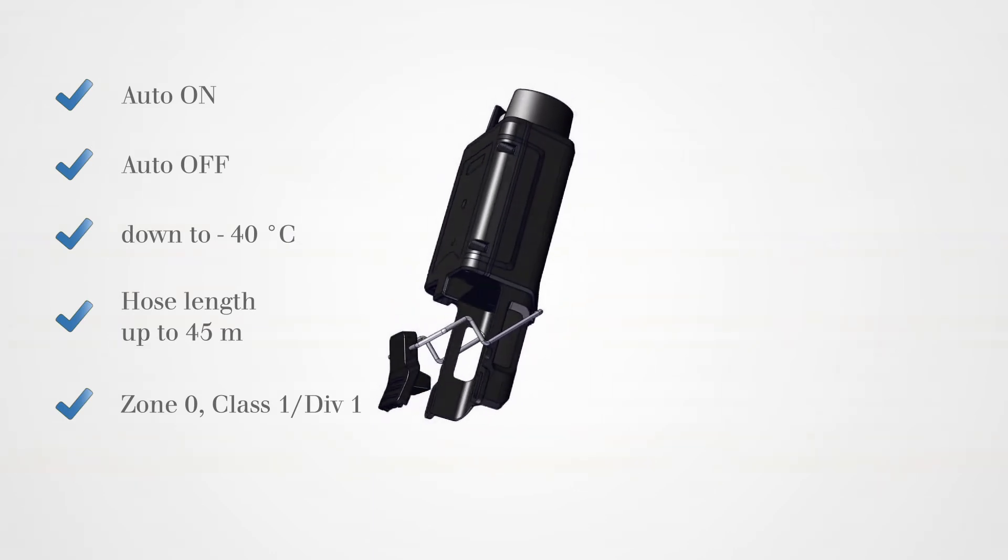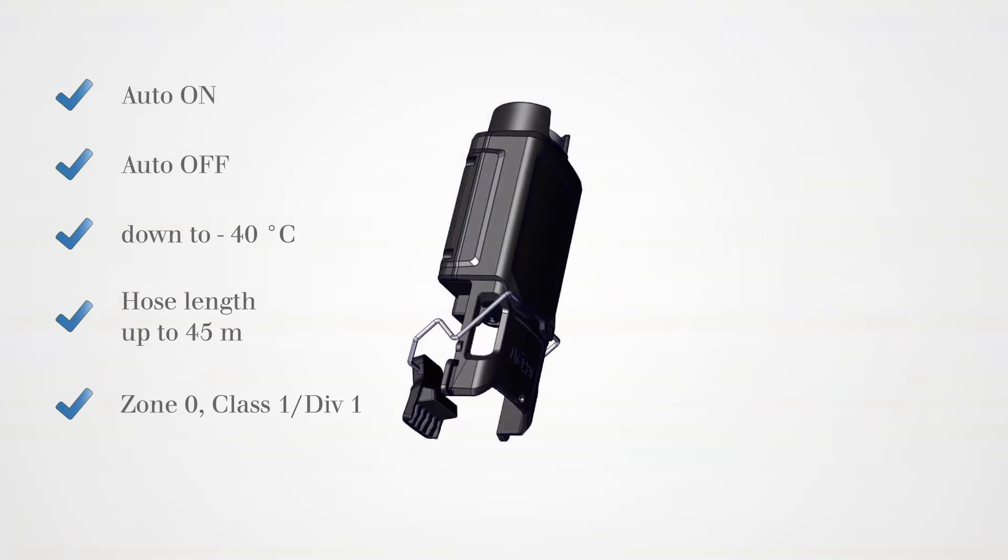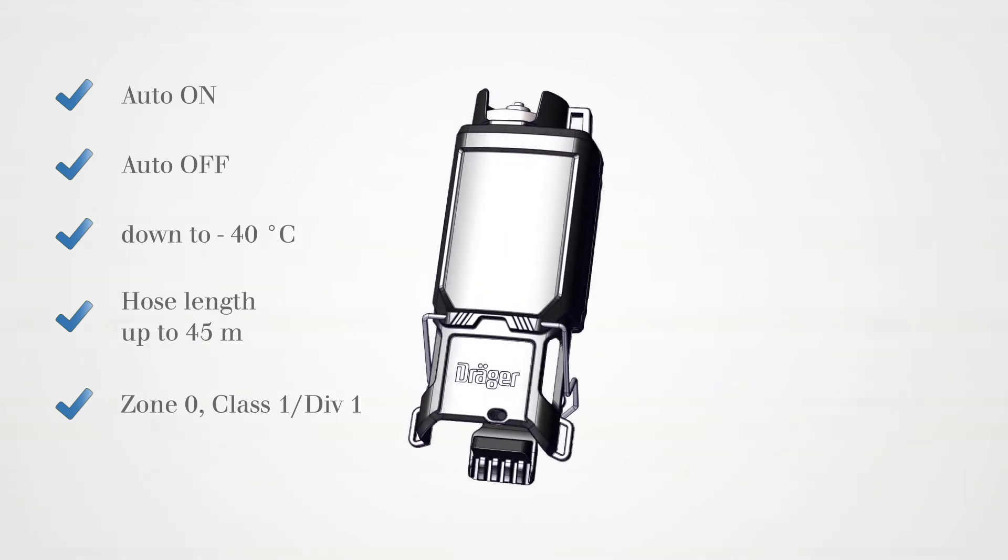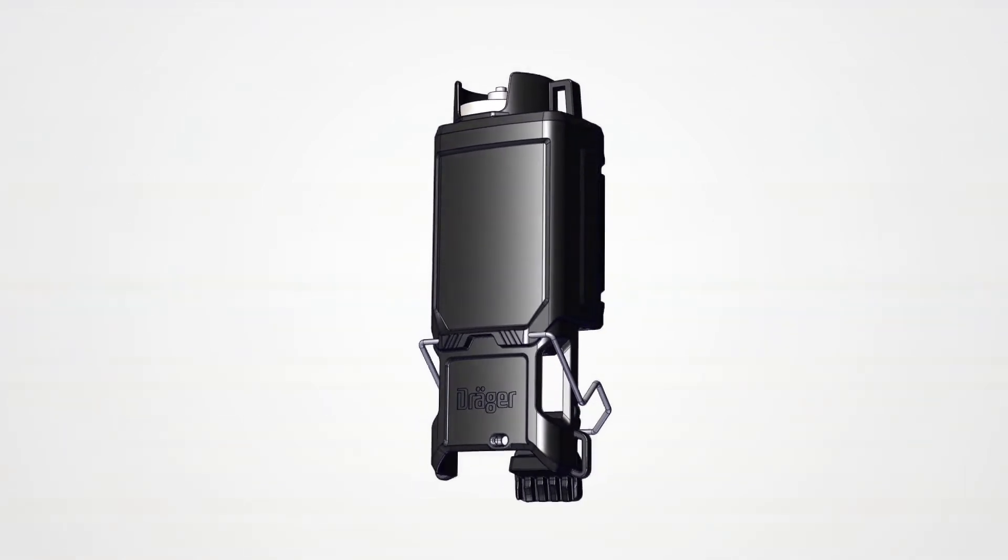The pump can be connected to sampling hoses up to 45 meters long. It can be operated in a Zone 0 or Div 1 hazardous atmosphere at a temperature of as low as negative 40 degrees.